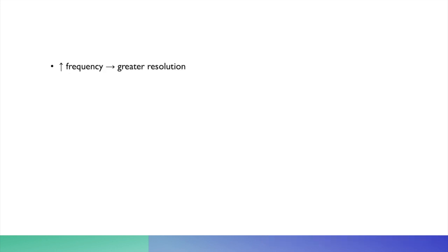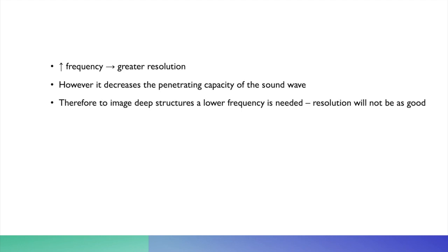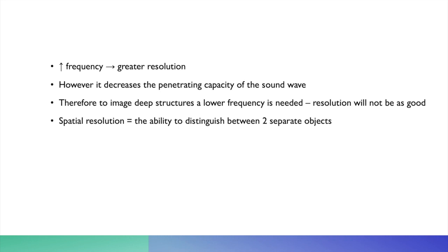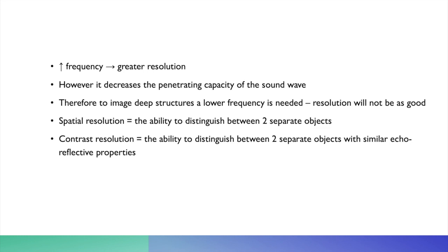A higher frequency of sound waves leads to greater resolution and a clearer picture. However, higher frequency reduces wavelength and reduces the penetrating capacity of each sound wave. To image deeper structures, a lower frequency with a larger wavelength is required, though the resolution will be less good. Spatial resolution is the ability to distinguish between two separate objects, while contrast resolution is the ability to distinguish between two objects with similar echo-reflective properties.